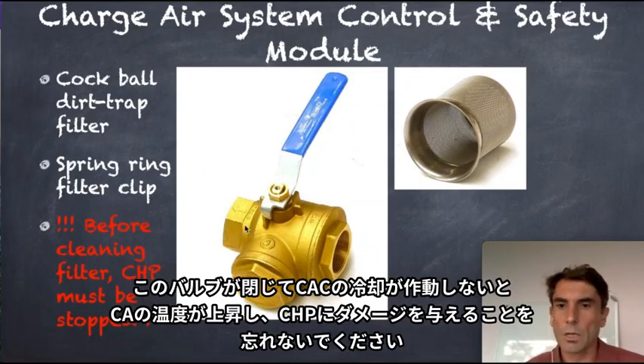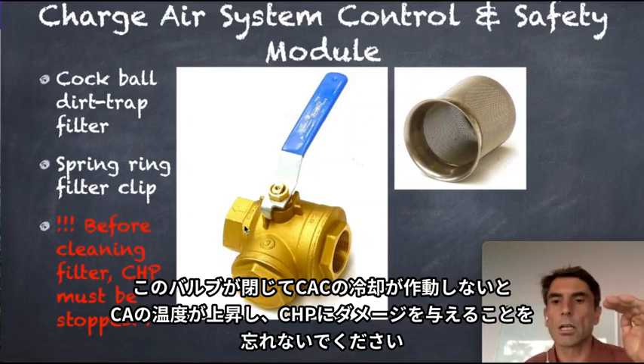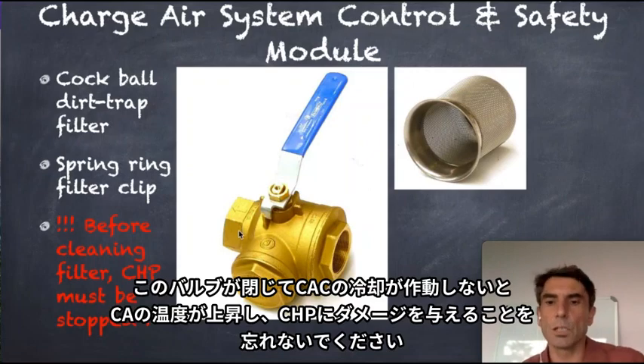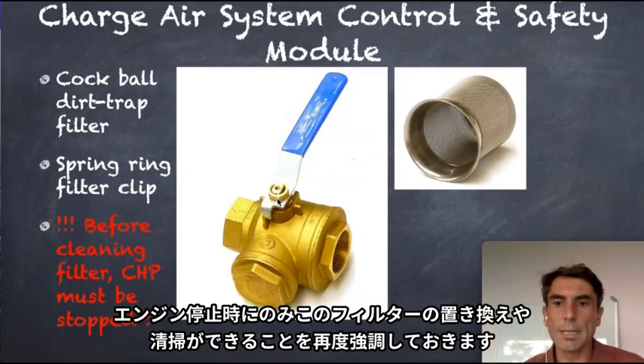So if you close the ball valve, there will be no cooling on the charger anymore, and the charger will heat up and can produce damages on the CHP. So please ensure that you only clean that filter if the engine is stopped.